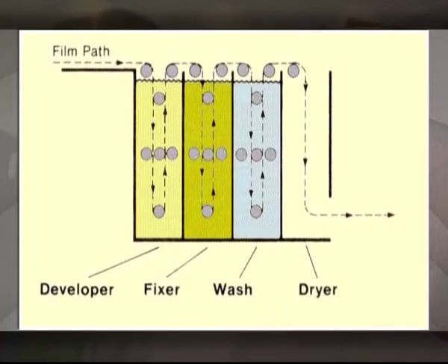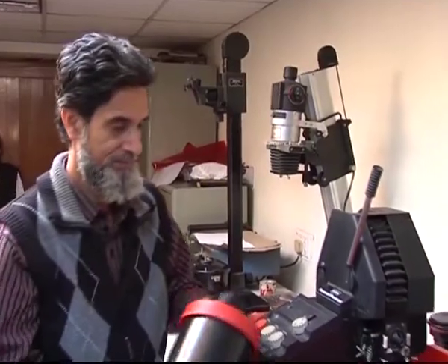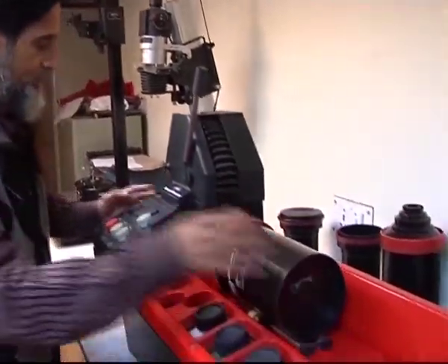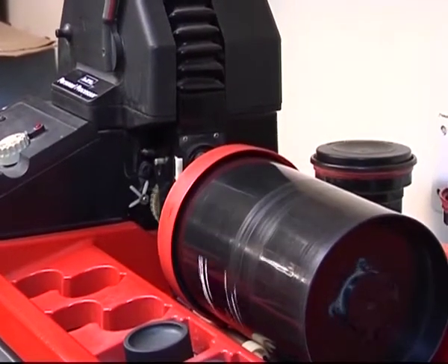Radiographic film is generally developed in an automatic processor. The 4 components correspond to the 4 steps in film processing. In a conventional processor, the film is in the developer for 20 to 25 seconds. All 4 steps require a total of 90 seconds.